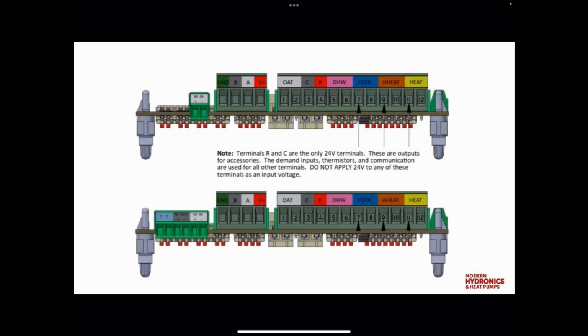The one caveat here is that you do need some type of system pump for the boiler. And a lot of ModCon boilers today have a system pump built in. But potentially you may need to add, whether it's a 009 or a 1558 or something, some small circulator to just handle that circuit from the boiler to our heat pump.